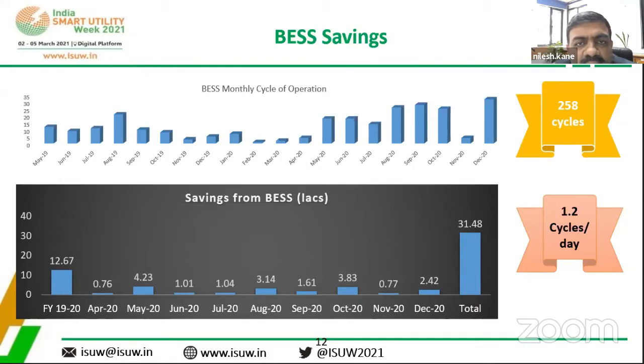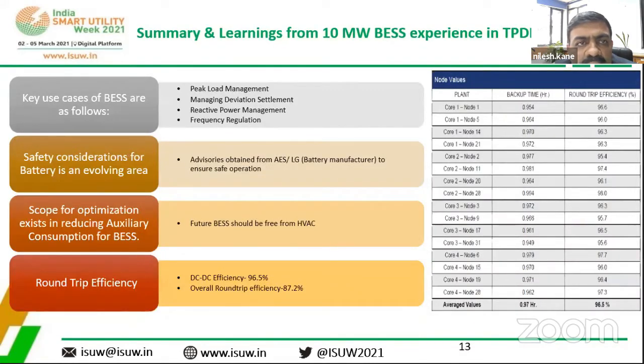These are the summary and learnings of the 10 megawatt battery. The key use cases have been peak load management, managing deviation settlement, reactive power management, and frequency regulation. Auxiliary consumption is an issue, and going forward we look for technologies with lesser auxiliary consumption. Efficiency we have seen is 96.5%. Hopefully technologies with better round trip efficiency, around 98-99%, will be a good solution for utilities to scale this up.